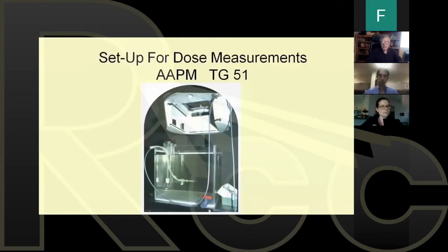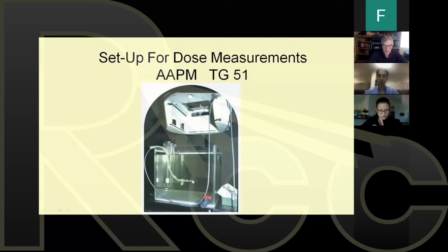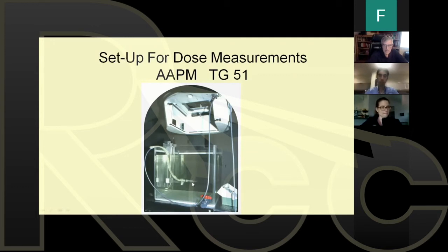This is a setup that I use in the States for TG51. I have a waterproof chamber. It's submerged in water up to a standard depth. We use 10 centimeters and a standard field size at a standard distance. So we're taking that thimble chamber, measuring it in water at a standard depth, and then using the calibration factor, NDW, which gets us from coulombs to centigray, to actually get the output of that beam in water. That is the absolute dose calibration of that machine.